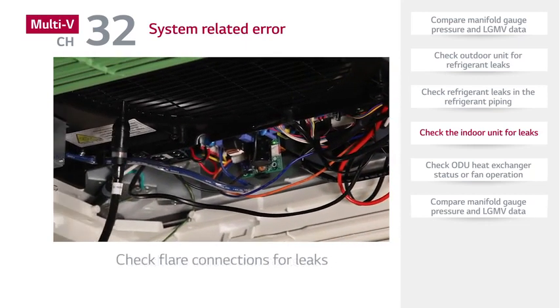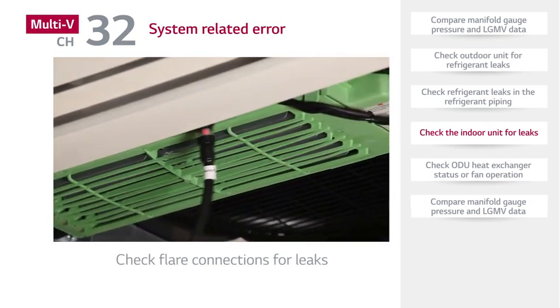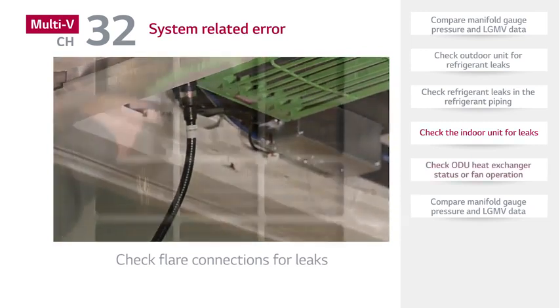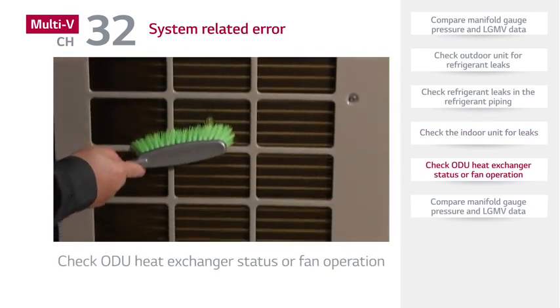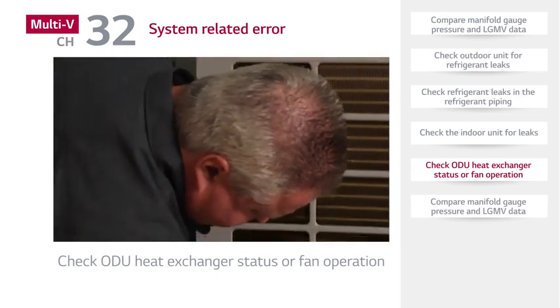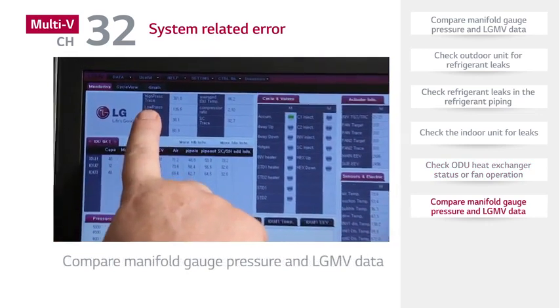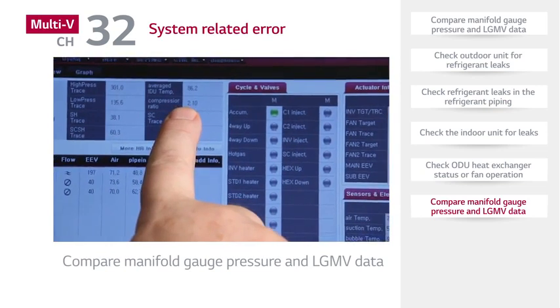Be sure to check the field flare connections for leaks. After checking the indoor unit, check the outdoor unit heat exchanger status or fan operation. After inspecting the outdoor heat exchanger and fan operation, check whether the LGMV data is normal.